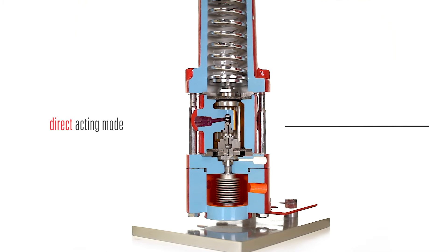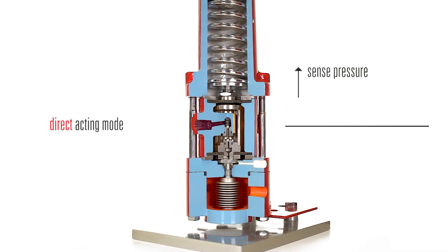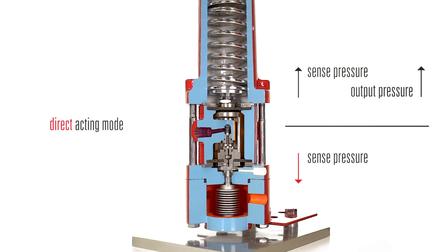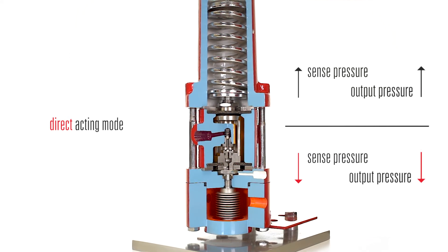In direct acting mode, an increase in sense pressure will increase output pressure to the valve, while a decrease in sense pressure will decrease output to the valve.